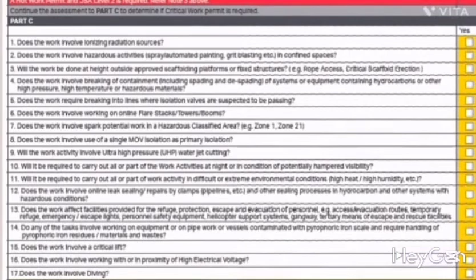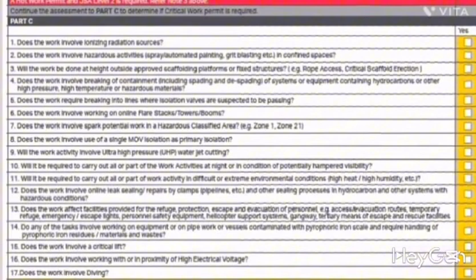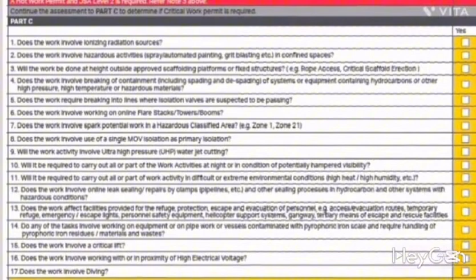If you need to perform any work at night, any type of activities, they will also fall under your critical work permit. Will it be required to carry out all or part of the work activity in difficult or extreme environments? If you need to work in high pressure, high wind, high temperature, or high humidity, all of that will be controlled under the critical work permit. At number 12, we have the work involving online leak sealing repair by clamps. If you need to perform any work in a live plant, install any valve or perform isolation, it will be controlled under the critical work permit.